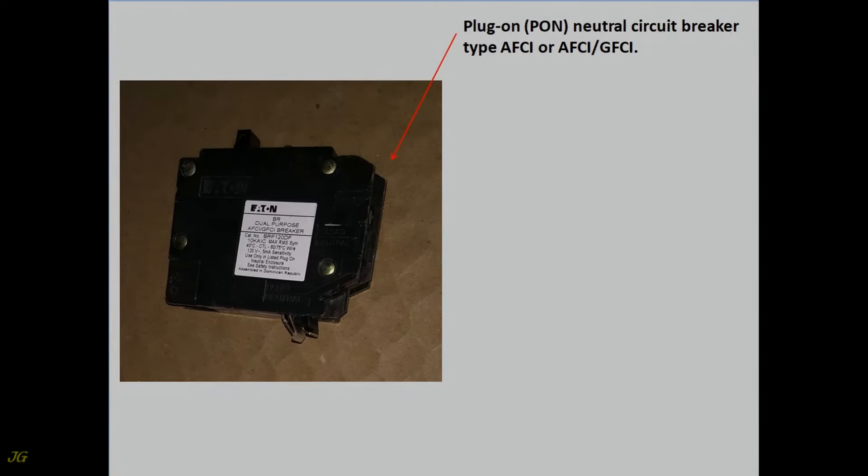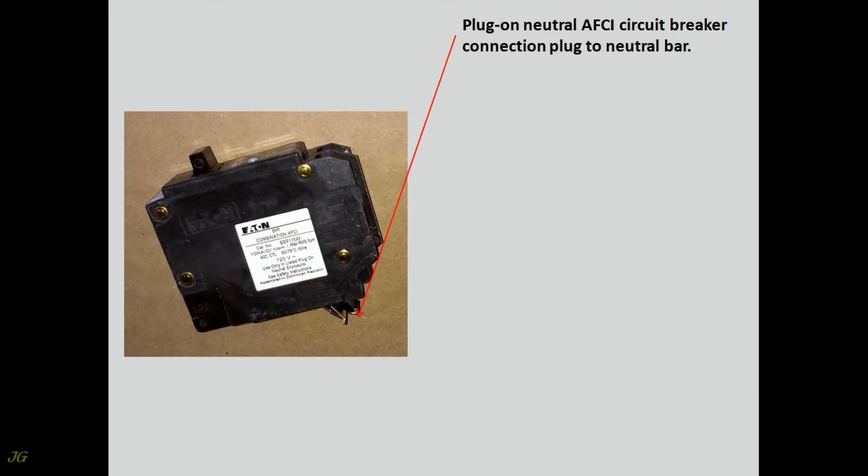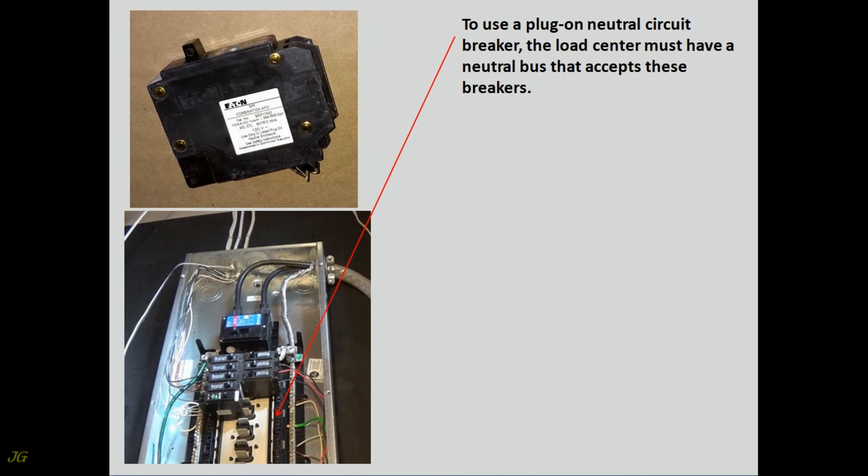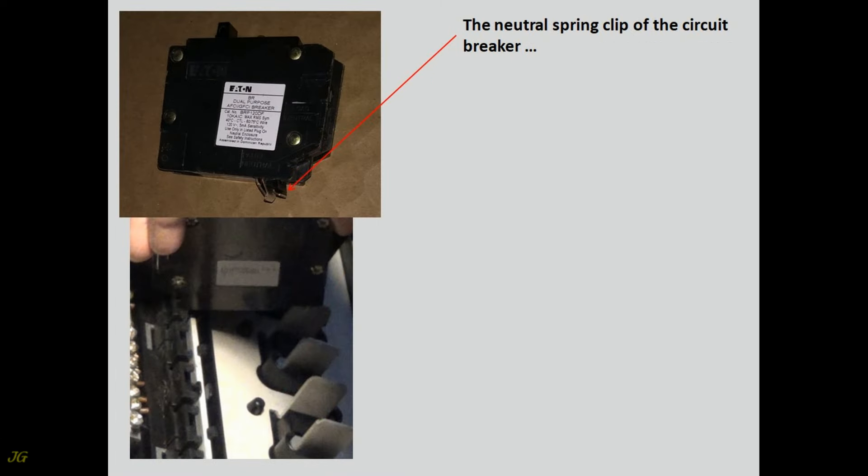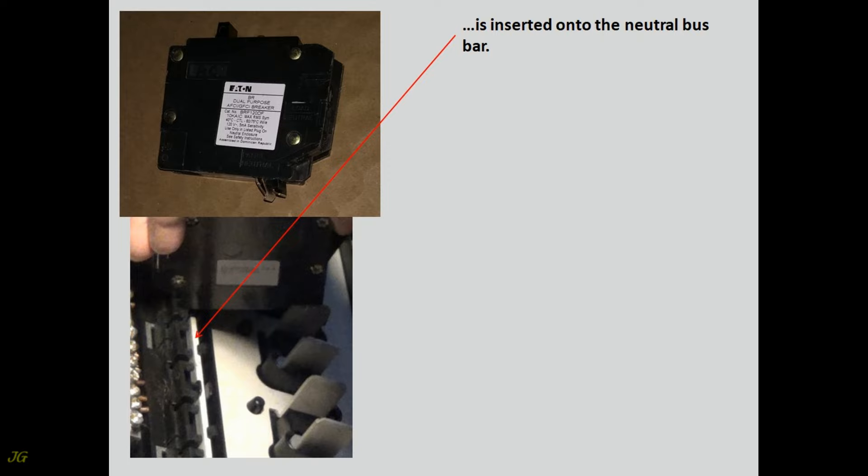Plug on, PON, neutral circuit breaker type AFCI or AFCI GFCI. Plug on neutral AFCI circuit breaker connection plug to neutral bar. To use a plug on neutral circuit breaker, the load center must have a neutral bus that accepts these breakers. The neutral spring clip of the circuit breaker is inserted onto the neutral bus bar.